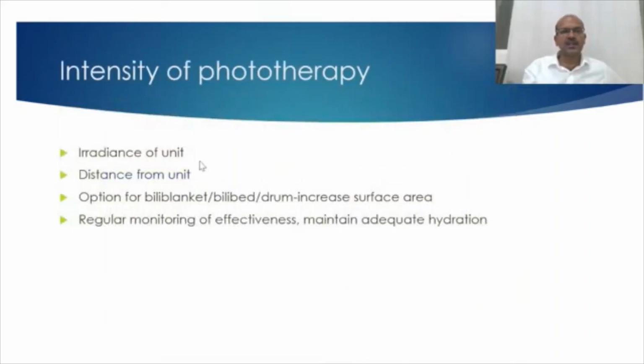So the irradiance depends on the radiance of the light, the distance from the unit, and the other important factor is the surface area. So anything that increases the surface area, like increasing the number of lamps, keeping a blanket underneath, having a lamp underneath the baby with a glass shield, perspex shield, having a drum phototherapy unit, all these are very effective ways.